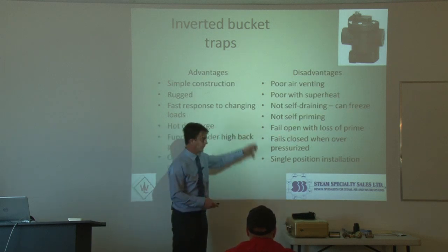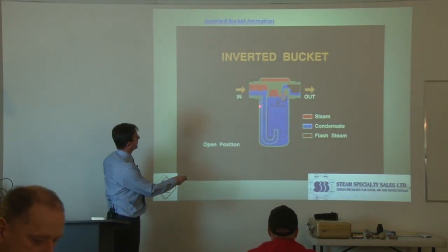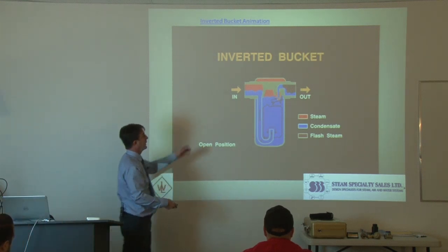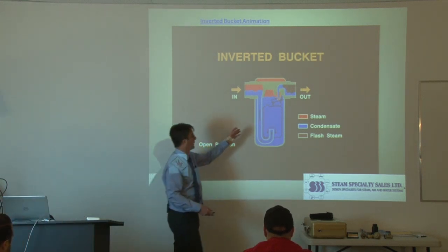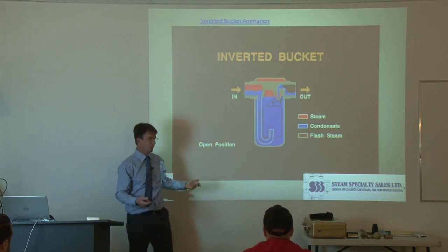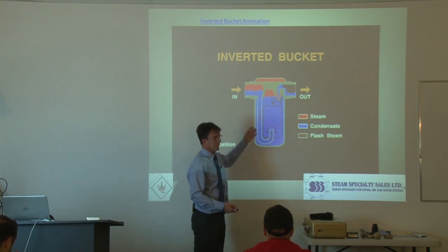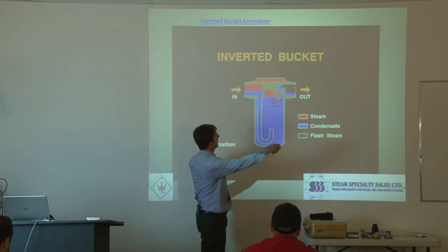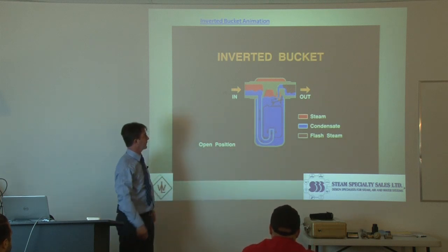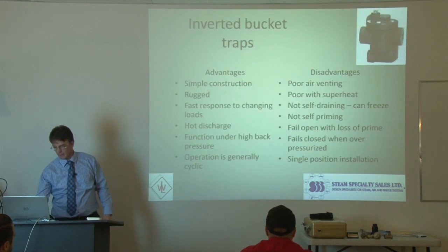They are also not self-priming, which means if the condensate inside is flushed out, they'll start leaking steam even though they're still in perfectly good mechanical operation. The fix, if a trap has lost its prime, is to shut the isolation valve on the outlet for a couple of seconds, let the trap fill up again, and it's back in operation. It doesn't happen that often, but you can lose the prime inside the trap.